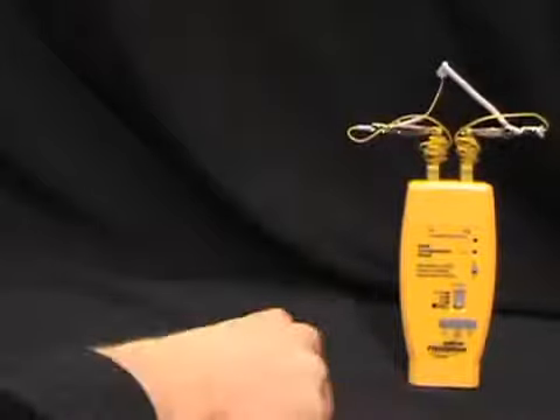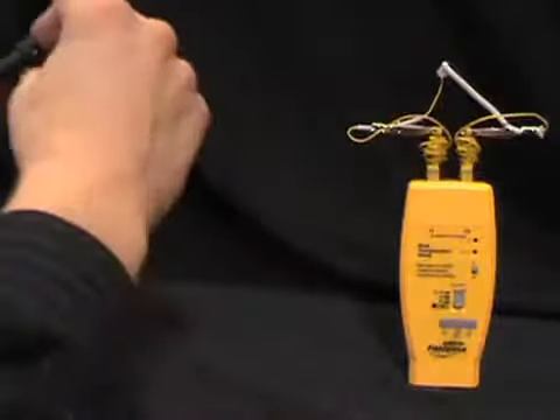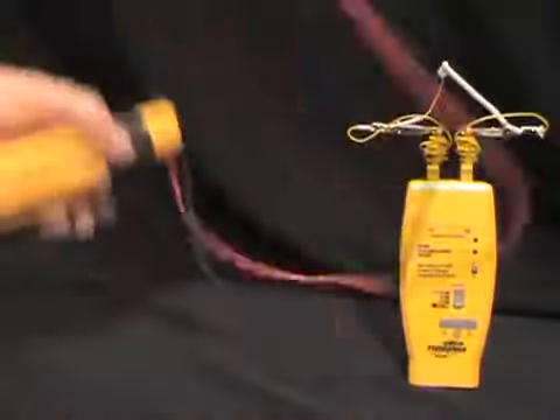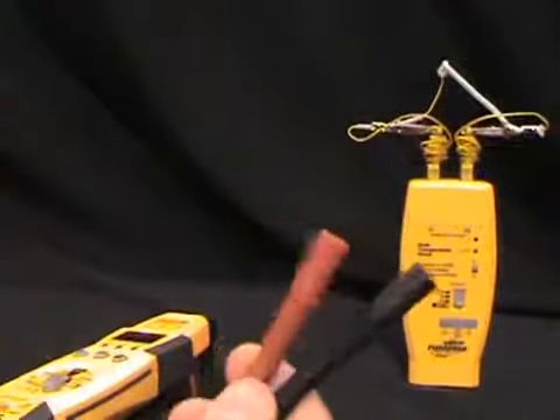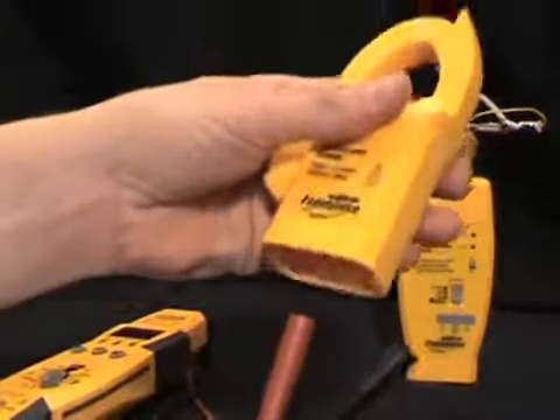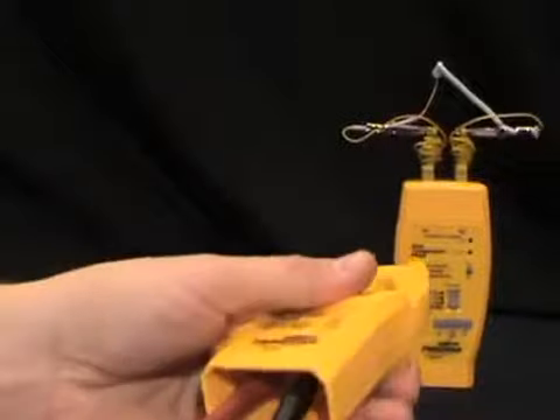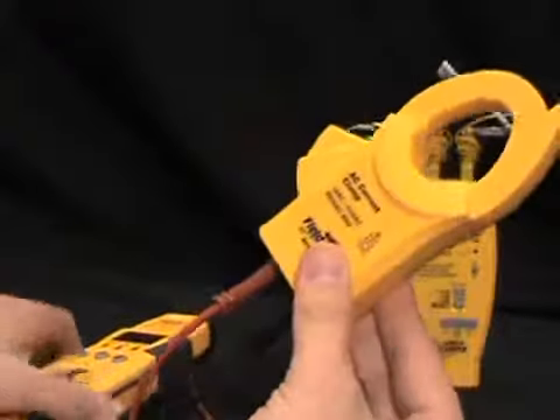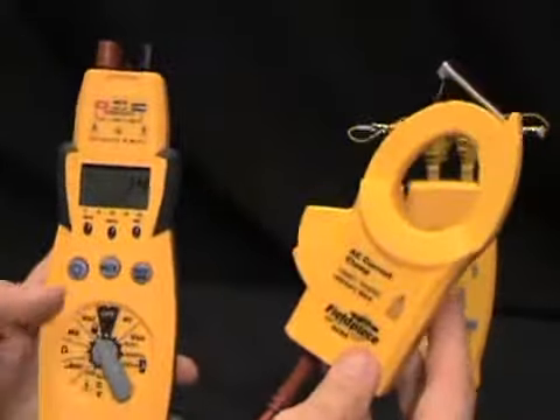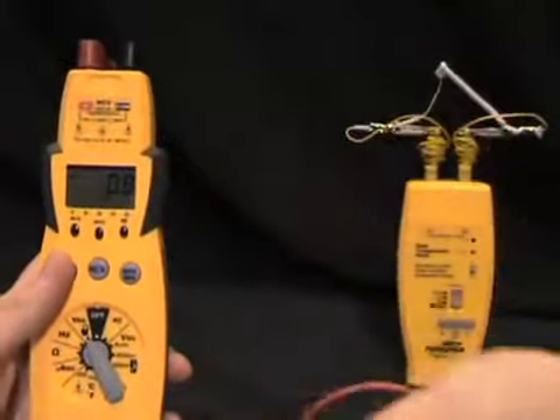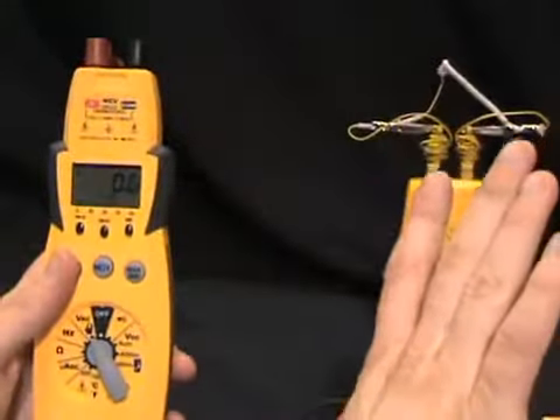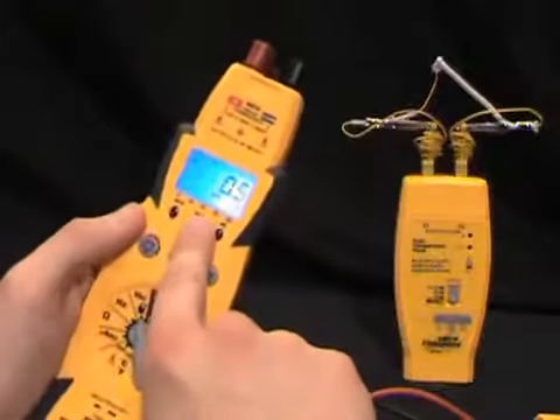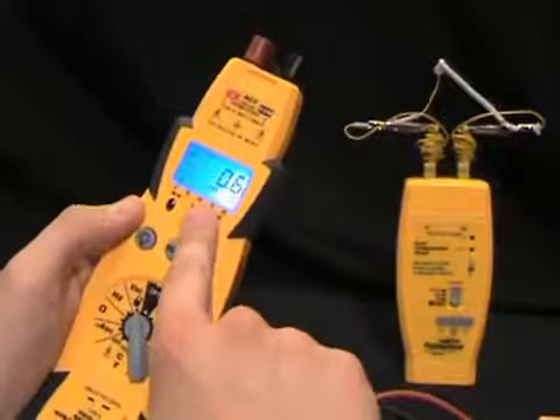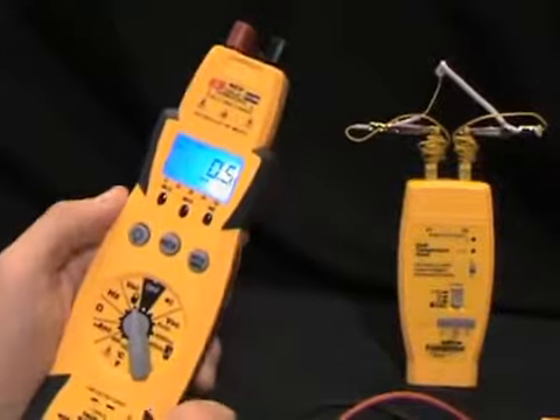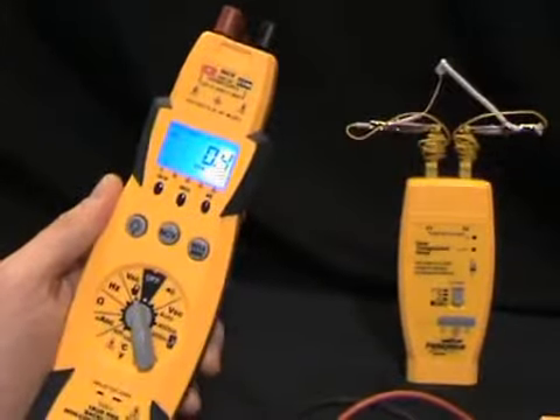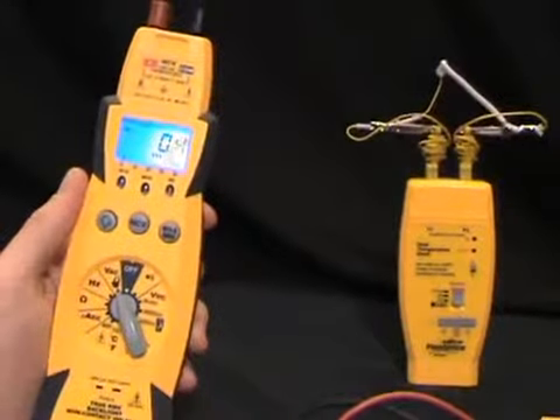But one of the biggest problems HVAC technicians have is being able to test amp draw in a blower motor. So what I can do with my leads, I can take my detached leads and plug them into our accessory heads just like this and remote our accessory head. So what I can do with my amp clamp now is stick this in the blower, shut the door, and read my meter outside of the blower just like that. Now I'm getting the correct amperage on my blower, and it's just a very convenient way to test blower amperage.